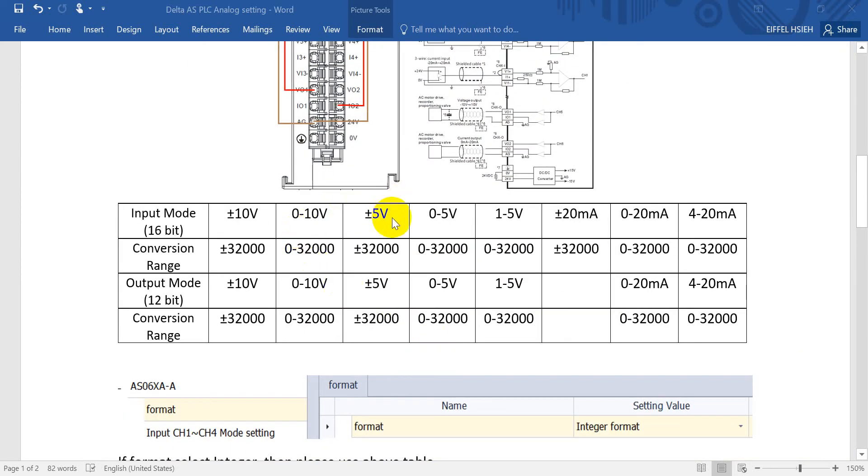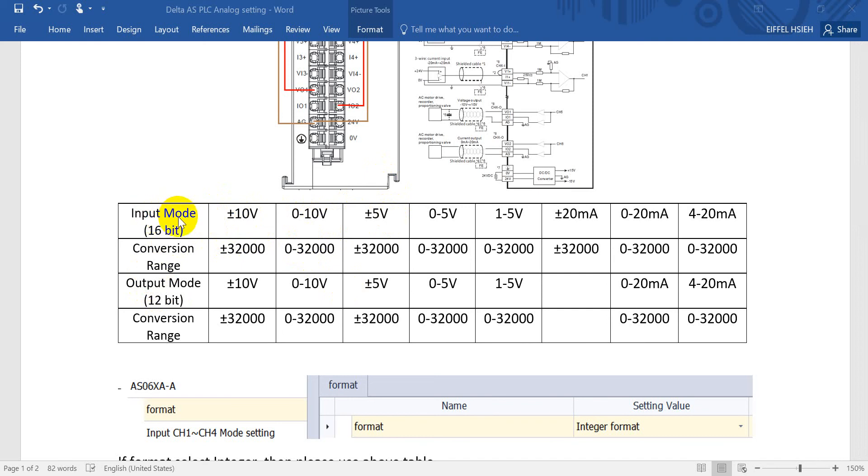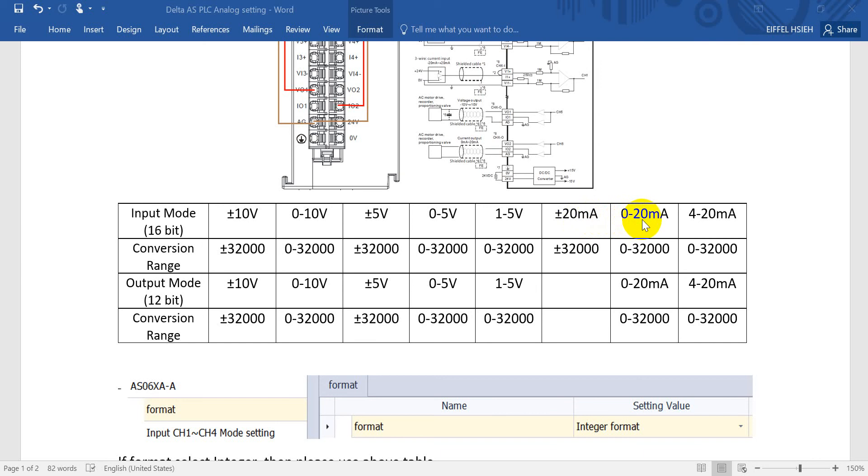We'll show you the input mode and output mode for Delta AS PLC modules. You can see the input modes. We provide plus minus 10 volt, 0 to 10, plus minus 5, 0 to 5, 1 to 5 volt, plus minus 20 milliamp, 0 to 20, and 4 to 20 milliamp. You can see the conversion range.